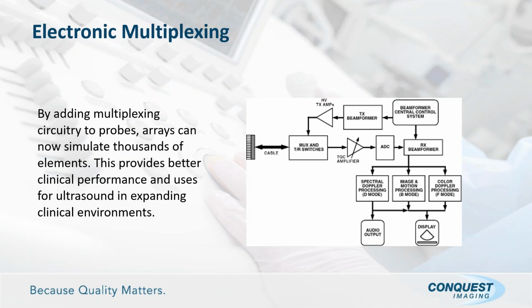Now, the multiplexing is a big one, but these have to be designed. It has allowed probes to be able to simulate thousands of elements as opposed to 128 elements of old, things like that, which certainly does help with the clinical performance. But again, it's got to be designed. The circuits have to be designed based on how you want the array to send, receive, what clinical application it's used in, etc. So all this again is just putting more cost into the device.